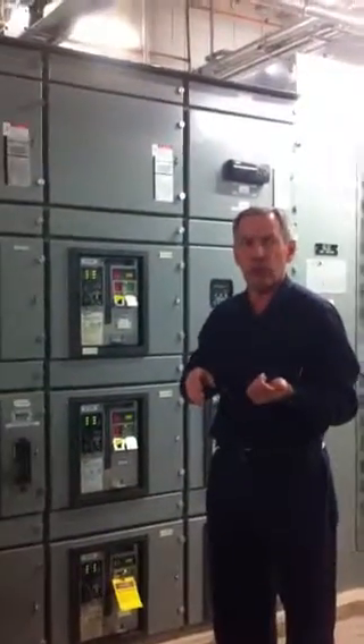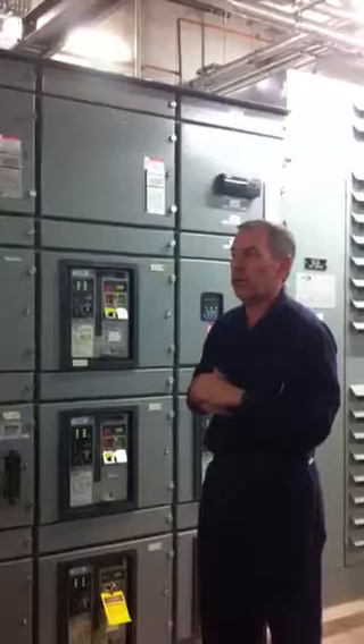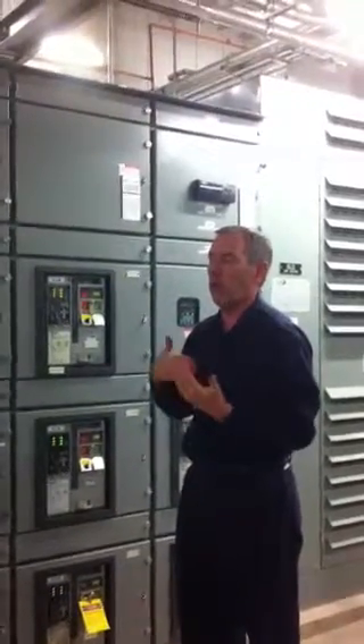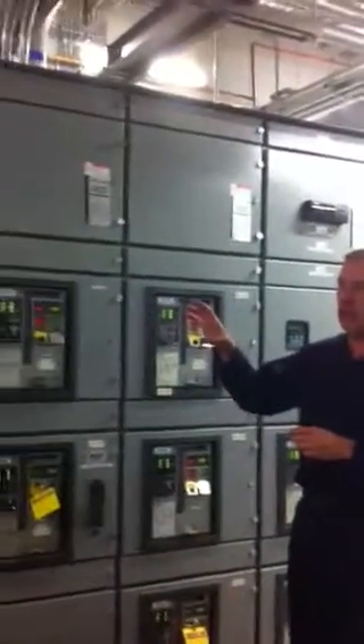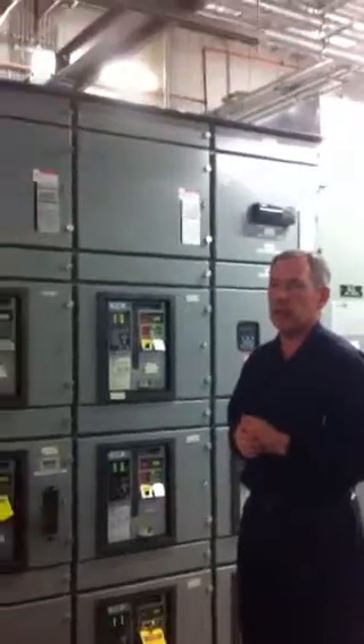One thing else I want to mention is we have been specifying TVSS, surge suppression, as close to the main incomings as possible, and I think you all have also started to put it on some motor control centers. Typically we never did this before, but with a lot more electronic equipment, electronic research equipment, we are trying to clamp any sort of surge or transient that does come into the building right at this board level.